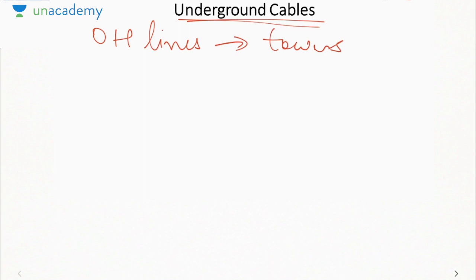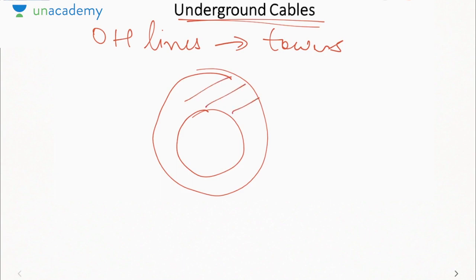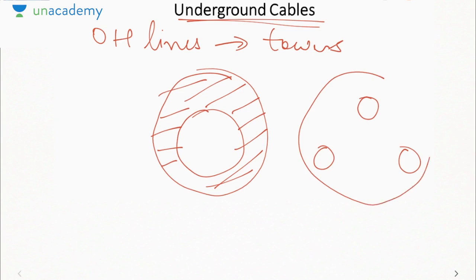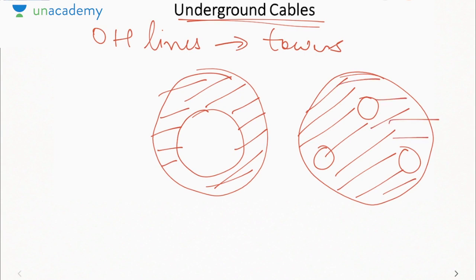Now, what is an underground cable? It is nothing but a conductor which is insulated throughout its length. If it is a conductor, then there will be insulation around the conductor. Or if there is more than one conductor in a cable, like 3 conductors, let us say for 3 phase, each conductor will have its own insulation. So that is how our underground cable basically works. The entire conductor is insulated and laid underground, and it is used wherever an overhead line is not possible.